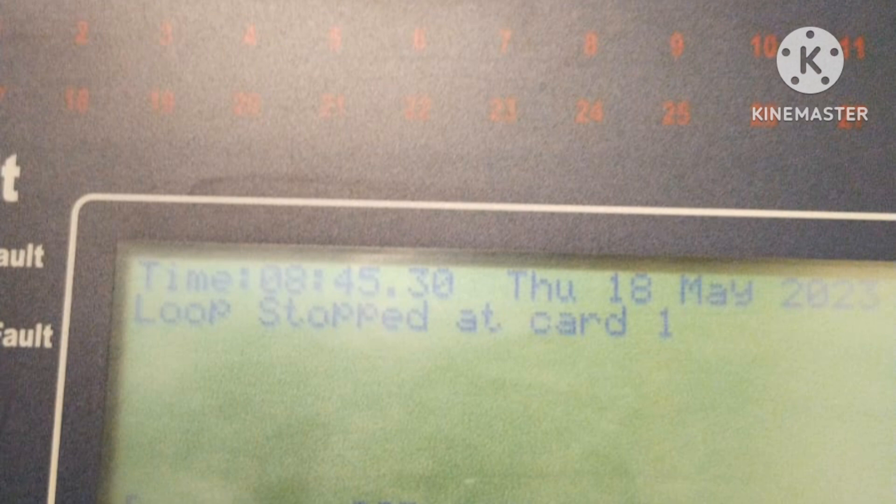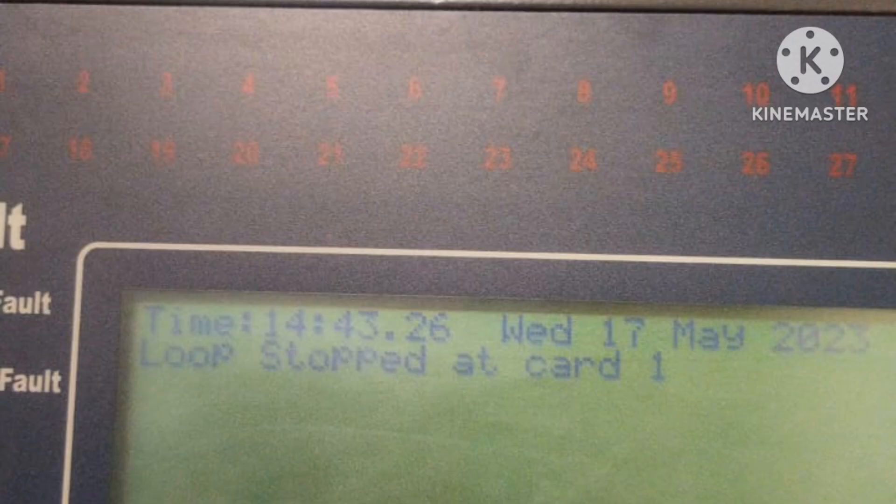If the short is not cleared, your loop will not restart. Many people ask me about 'loop stopped at card' — how to fix it. Sometimes it is due to a disablement: your card is disabled, or some part of your panel is disabled. So first, also check the disablement — go to Info and check what disablements are active.